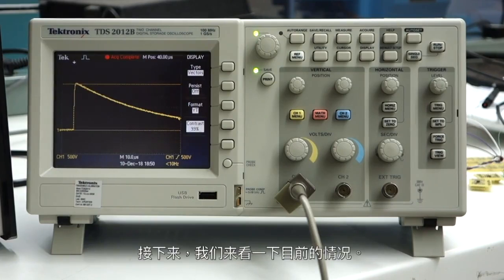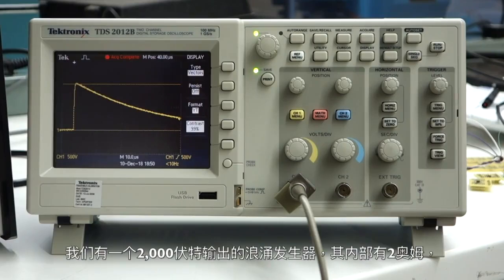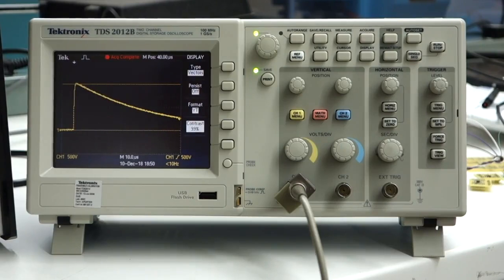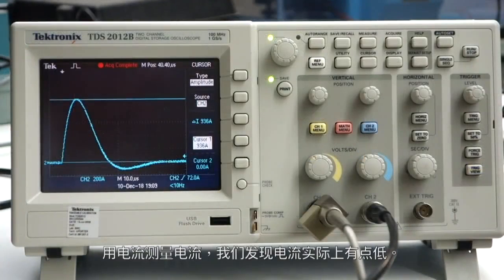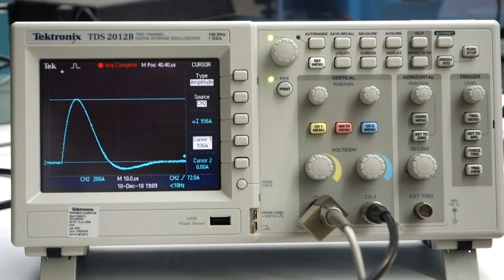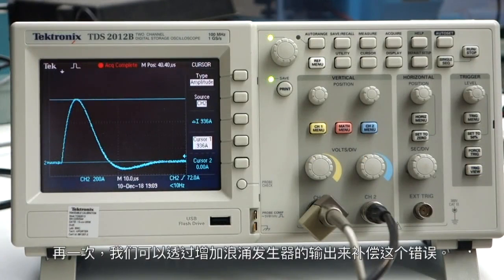Next, we're going to take a look at the current. We have a 2000 volt output of the surge generator, and it has 2 ohms internally, so we should be looking for 1000 amps peak. Measuring the current with the current coil, we discover the current is actually a little low. Once again, we can trim this error out by increasing the output of the surge generator to compensate.